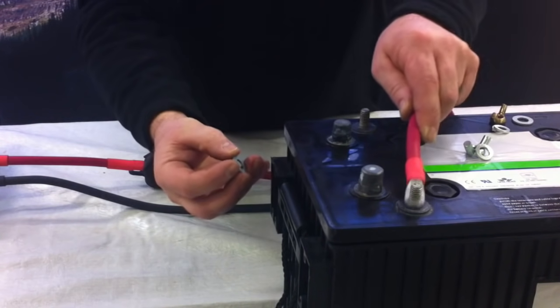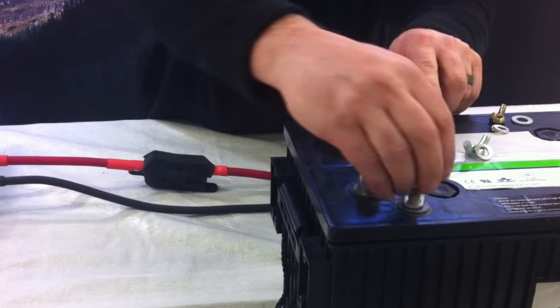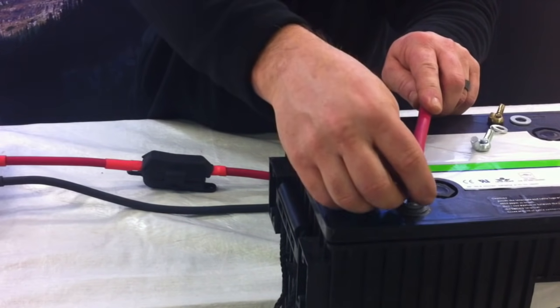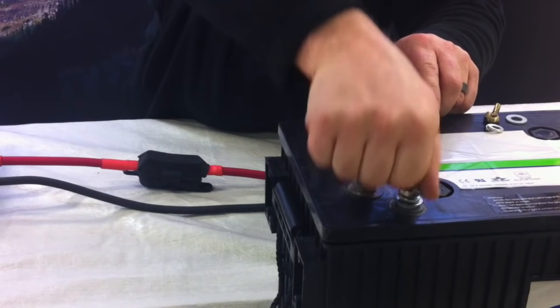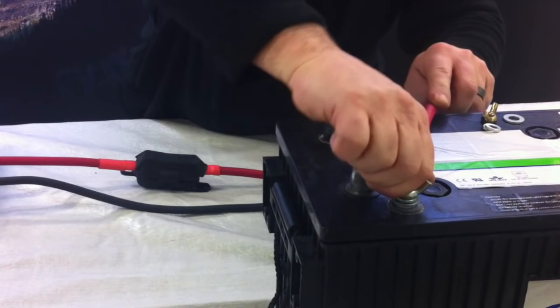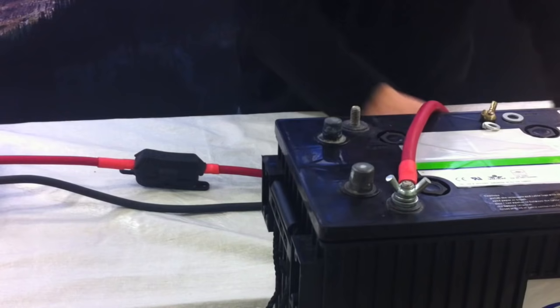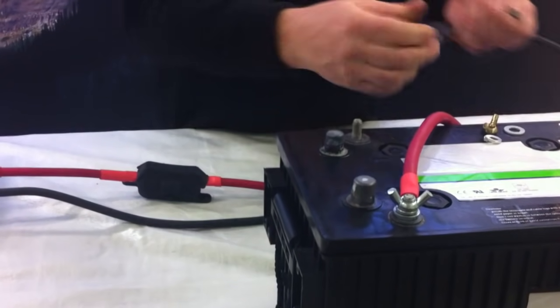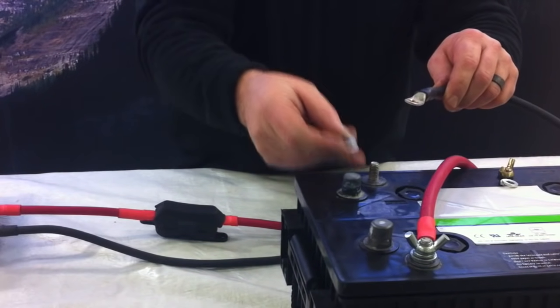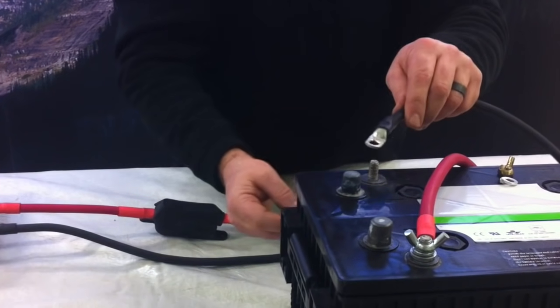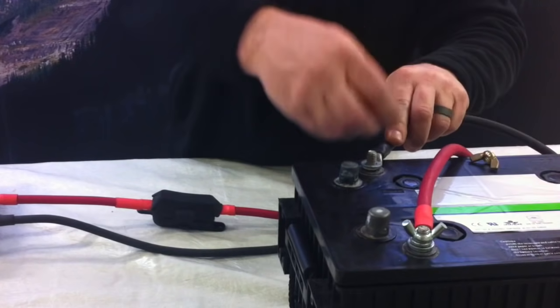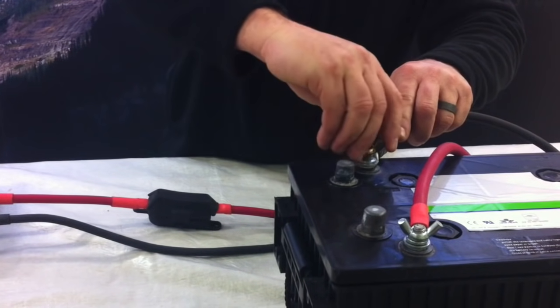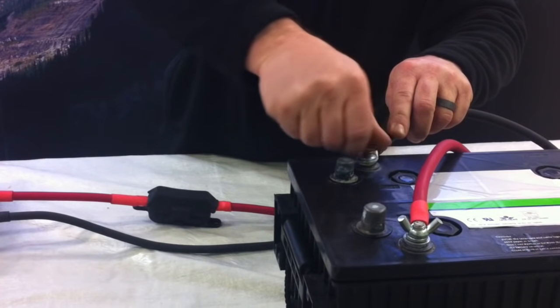So lug down first, flat washer on top, lock washer, and then we can move on to the negative. Again making sure that nothing comes in between the battery terminal and the lug. The lug going down first, the flat washer, the lock washer, and then the wing nut.